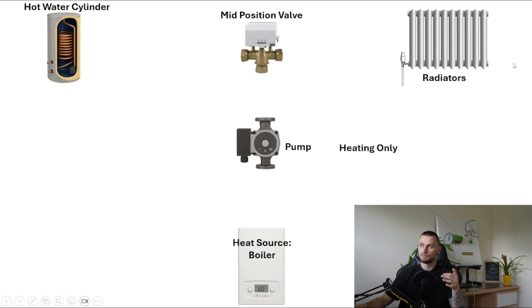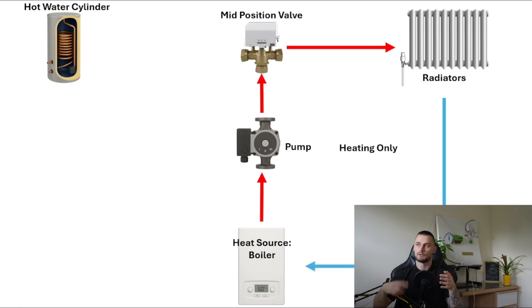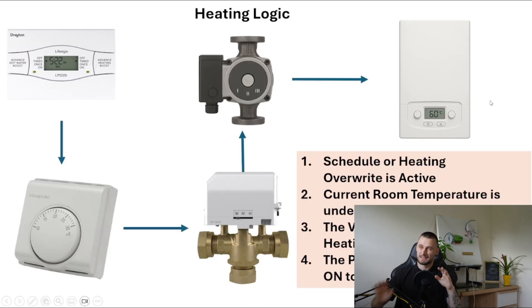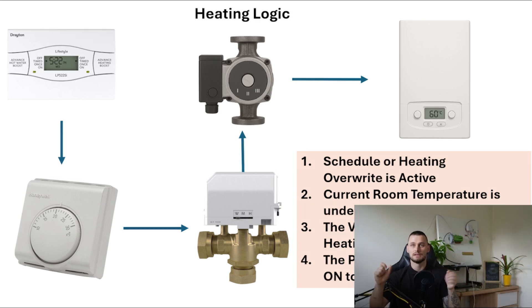Much the same logic applies for heating. If hot water is already satisfied, the system circulates hot water only around the radiators and towel rails. The difference is that instead of the cylinder stat, we use the room thermostat to decide whether heating is demanded — whether the temperature is below whatever we've set — and then it does basically the same thing.